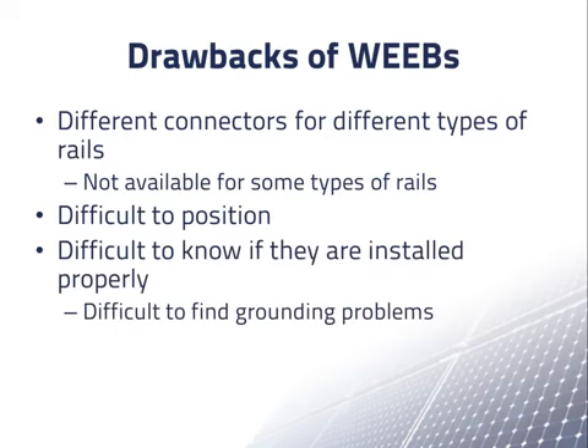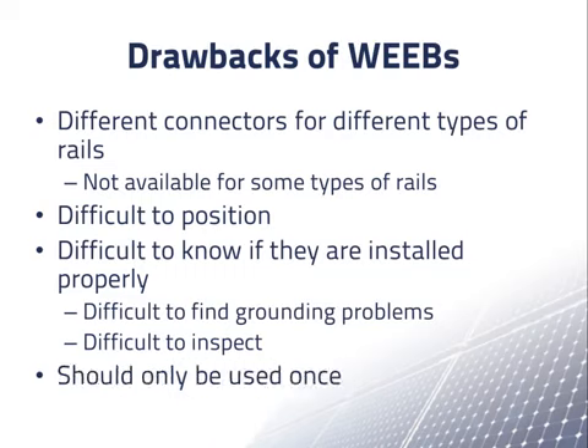Once a WEEB connector is installed, it is difficult to know if it is positioned properly or even there at all. So if a grounding problem is detected, it can be difficult to figure out where the bad or missing connection is located. In addition, electrical inspectors like to see that the grounding is done properly, especially since they know to look for bad grounding. They may not be happy with grounding connections in places where they can't be seen during an inspection. Some inspectors have not permitted them. And as we've mentioned before, WEEB connectors should only be used once. This means that you need to install new ones when replacing a module.